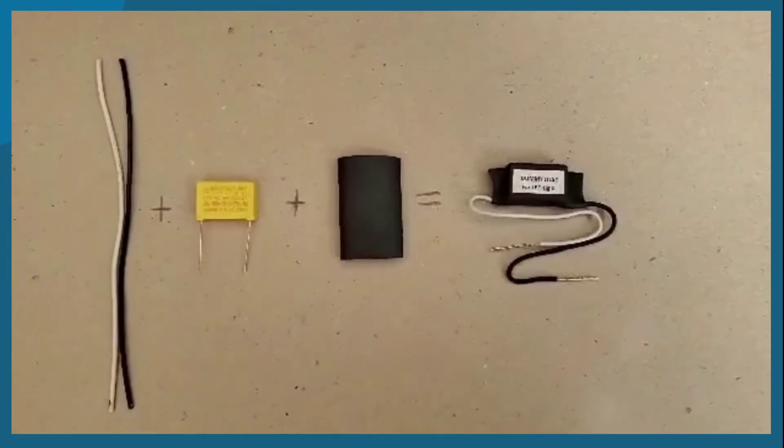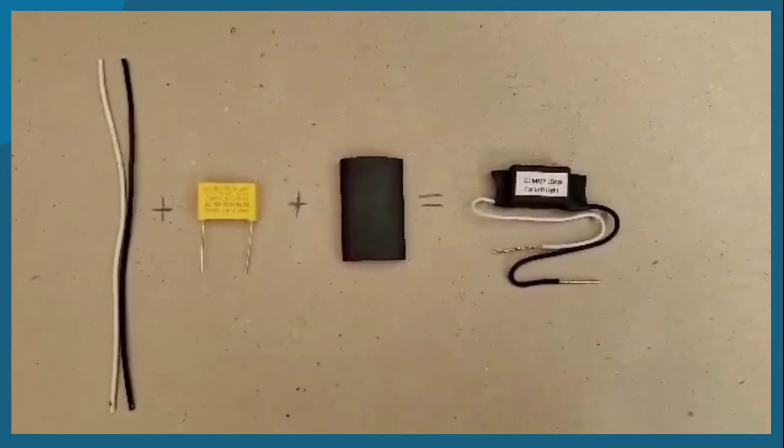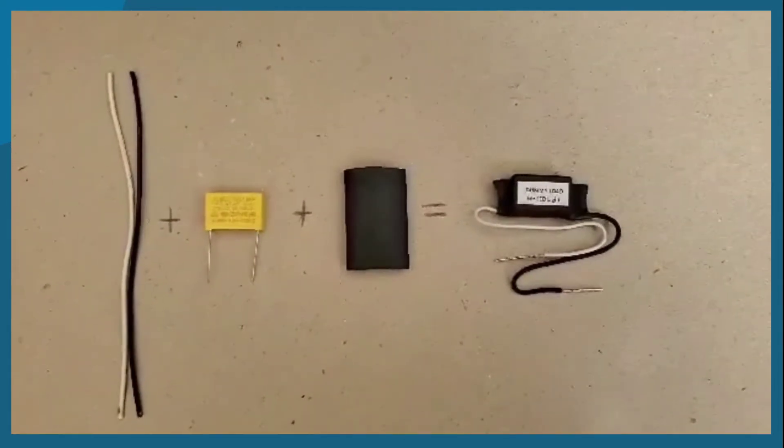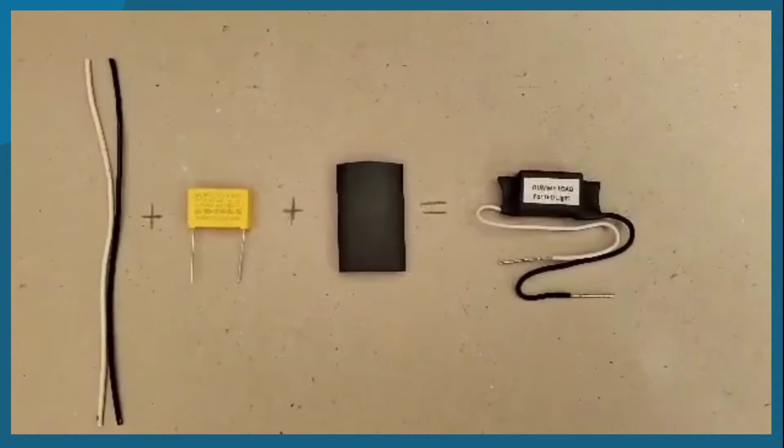We have to create a dummy load because electronic switches need minimum load to be able to turn off. This dummy load will provide this minimum load, but it's really almost no power consumption. You don't have to worry about that. It's just minimum load for electronics to work.